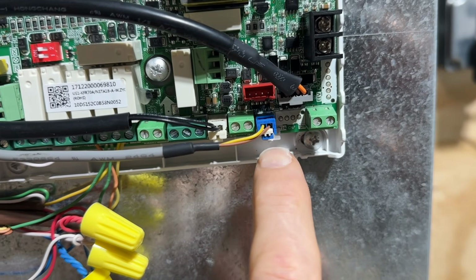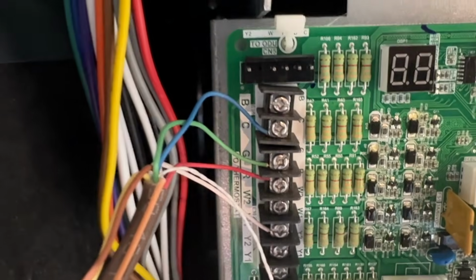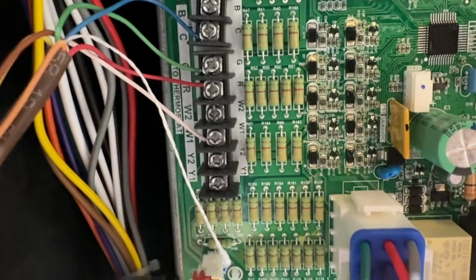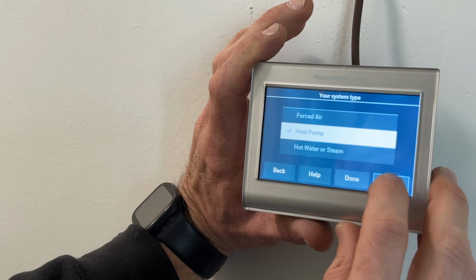A couple quick troubleshooting tips here. If your system doesn't start up, maybe you forgot to install the T1 sensor. That is one thing that will keep this entire system from operating, so make sure you have that installed in the return airflow or your system won't operate. If your blower doesn't come on, start with your G wire. Maybe you didn't get it connected properly. Maybe you forgot to connect the G from the interface to the furnace. If your outdoor unit doesn't come on, check your Y wire. And if your auxiliary heat is acting weird, check your W and/or your thermostat settings.